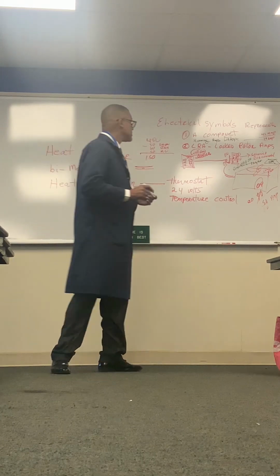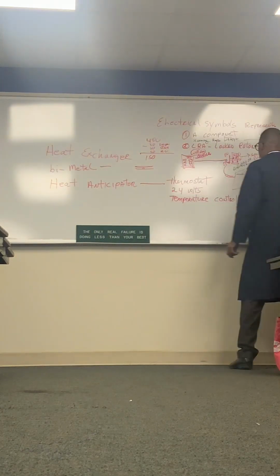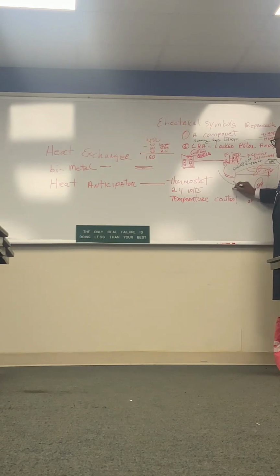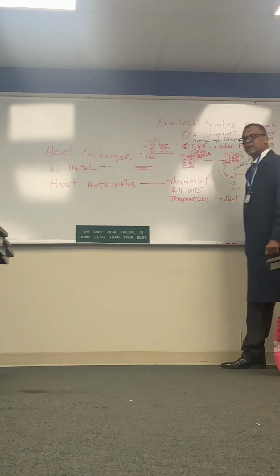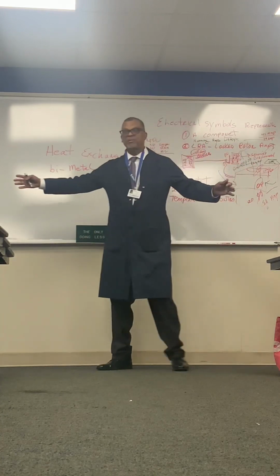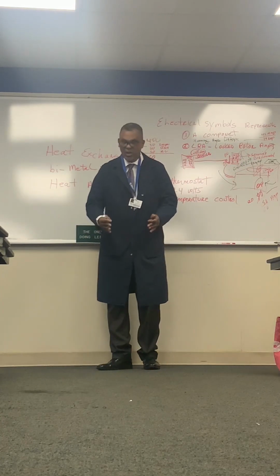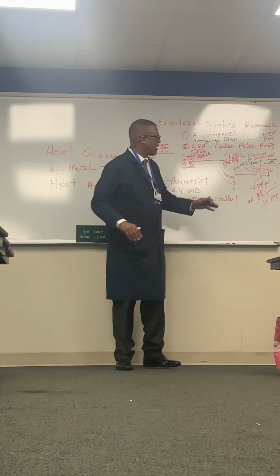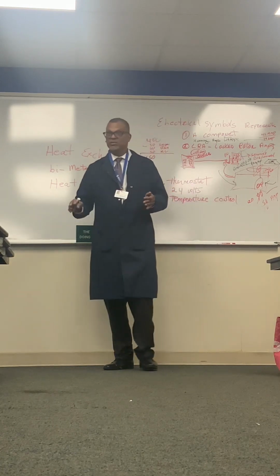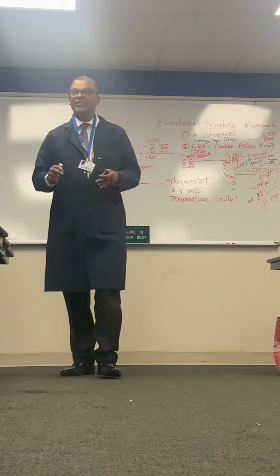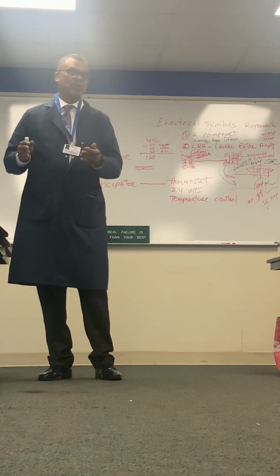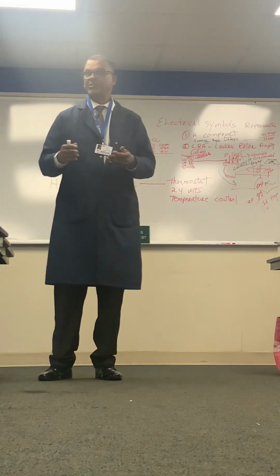The cooler it becomes. So the air from ambient goes in the sides of the vents on an air conditioner, and it dissipates from the top. So it's bringing this ambient that's cooler, sucking through, going through these coils, all of these coils on an outdoor unit, you'll learn more about, and then it cools those coils to below the temperature that it came.